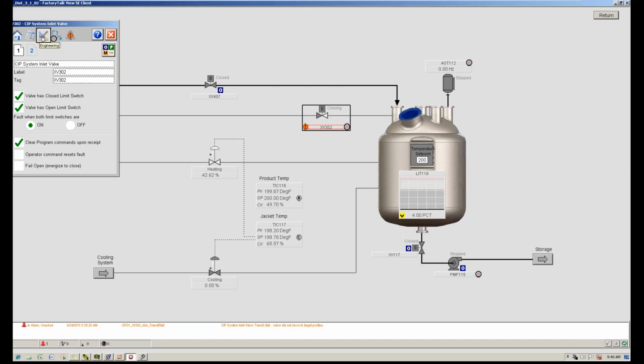problem as required. If I determined that the limit switch in the field was faulty and I needed this valve to operate so that I could keep the process running, I can come in here and just say, well, it no longer has a limit switch. Operate the valve without a limit switch.